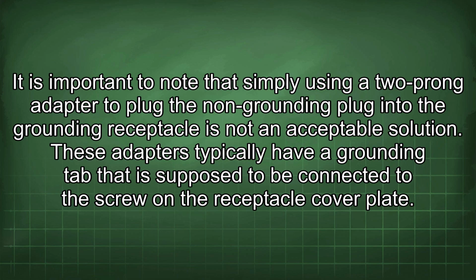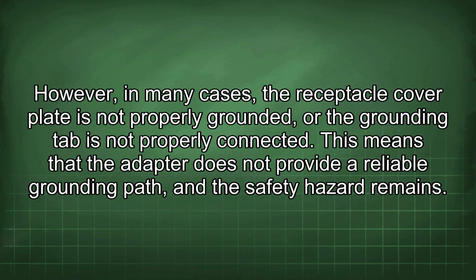These adapters typically have a grounding tab that is supposed to be connected to the screw on the receptacle cover plate. However, in many cases, the receptacle cover plate is not properly grounded, or the grounding tab is not properly connected. This means that the adapter does not provide a reliable grounding path, and the safety hazard remains.